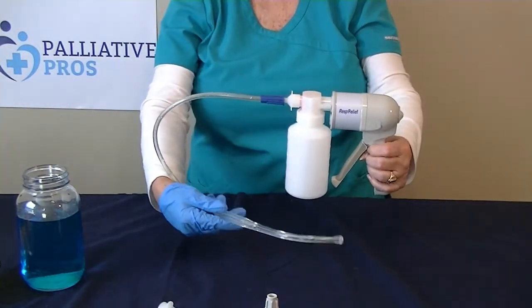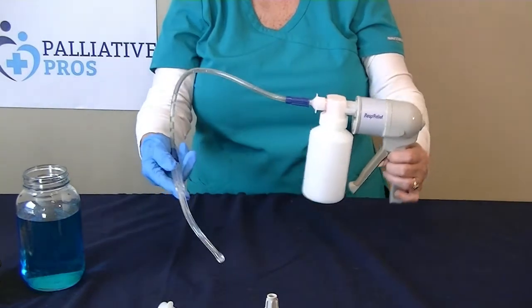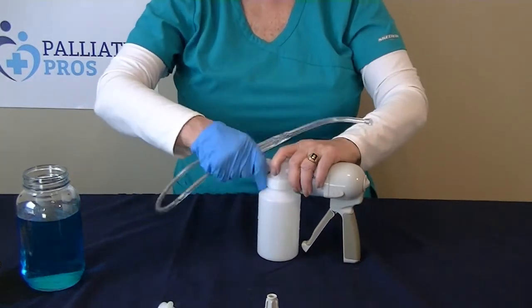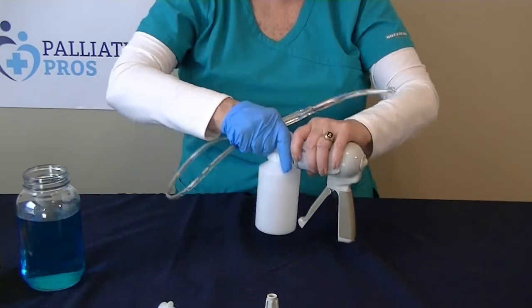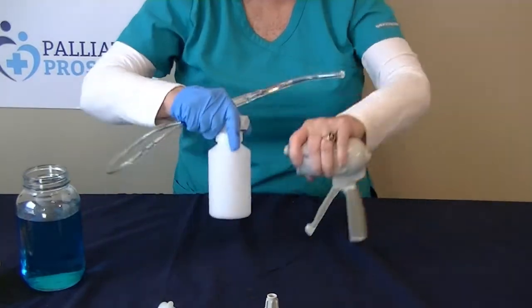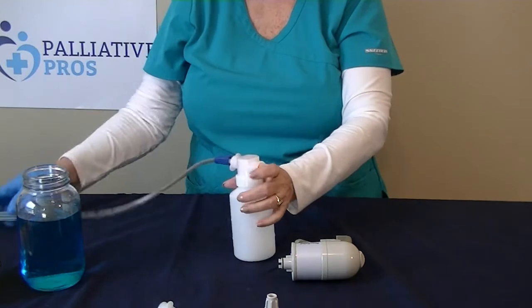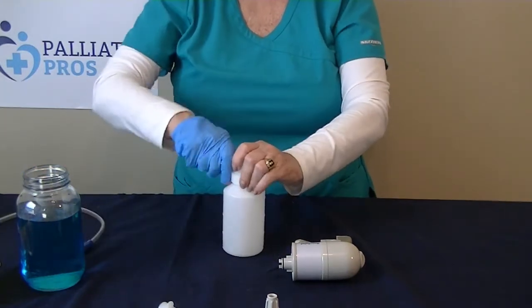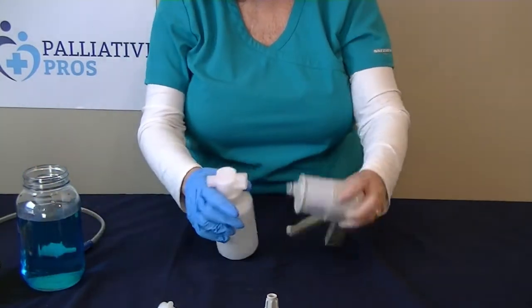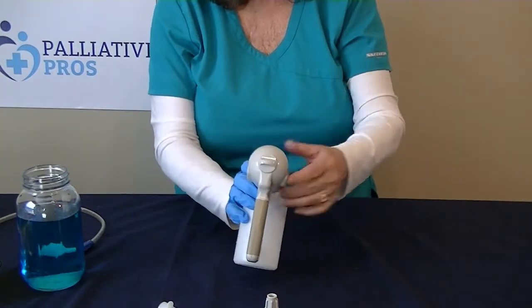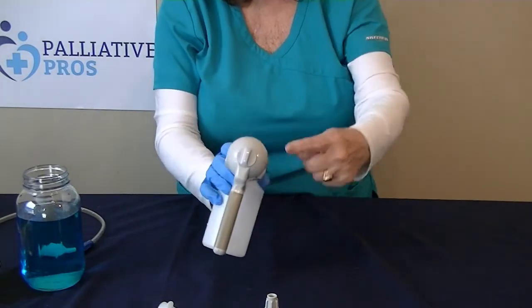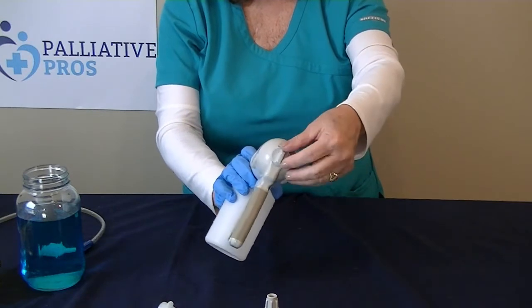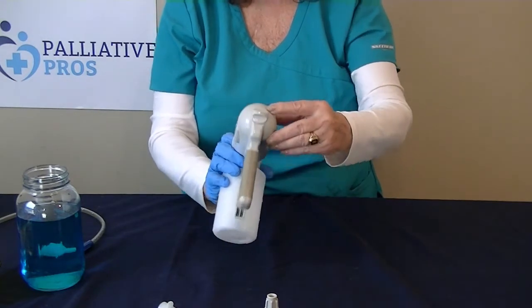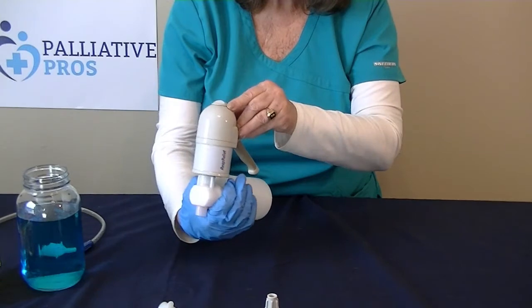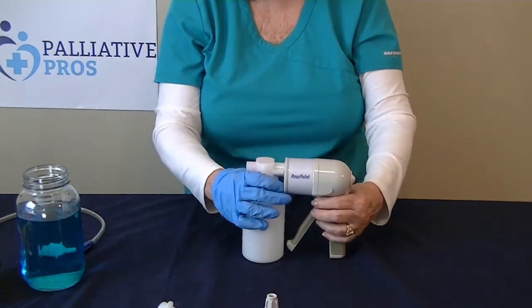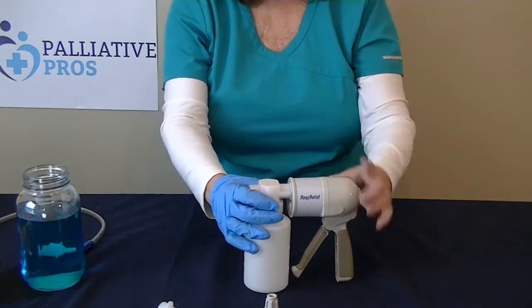How easy is that? Next, let's perform the basic pump functional test before each use and following cleaning and reassembly for reuse. Check the stroke adjustable lever on the back of the pump for the correct setting of pressure. 100% for adults, 50% for pediatrics. Okay. Next, mount a collection jar with cap to the pump.